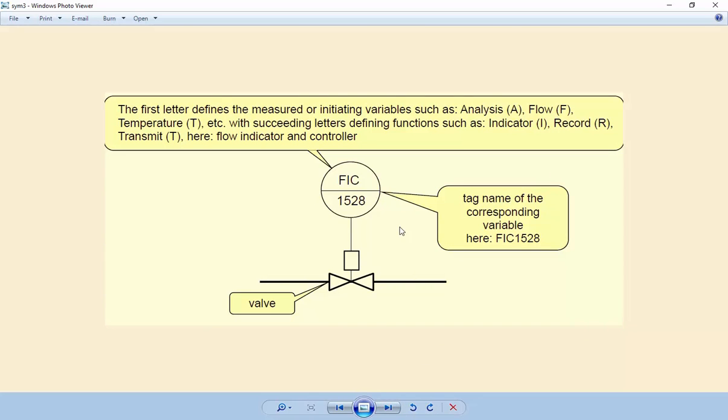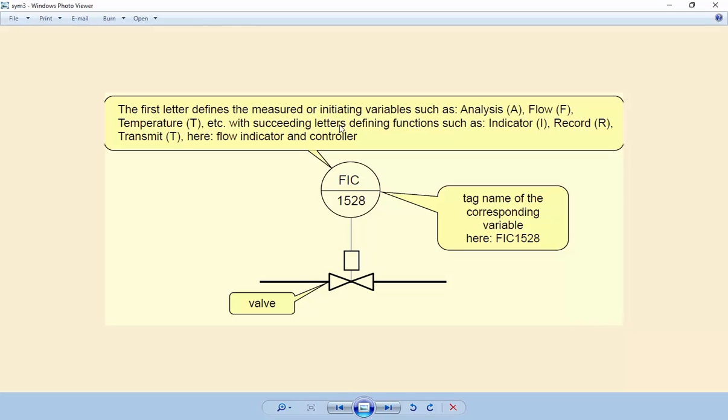In P&ID diagrams there is a number as well as a name. The first letter defines the measured or initiating variables such as Analysis (A), Flow (F), Temperature (T), etc. Succeeding letters define functions such as Indicator (I), Record (R), Transmit (T). Here F is for flow, I for indicator, and C for controller.